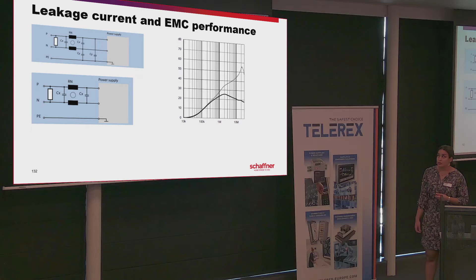And another aspect that is important in the medical standard is the means of protection. So whenever we have a requirement about a 2 MOPP component when it comes to patient-coupled device, so if you have a medical device that is related directly to the patient, you need to have a class 2 isolation. This is a double isolation. And in order to respect this, we have filters that already include this kind of IEC inlet.